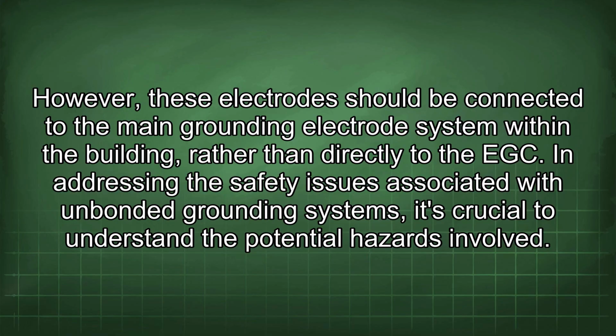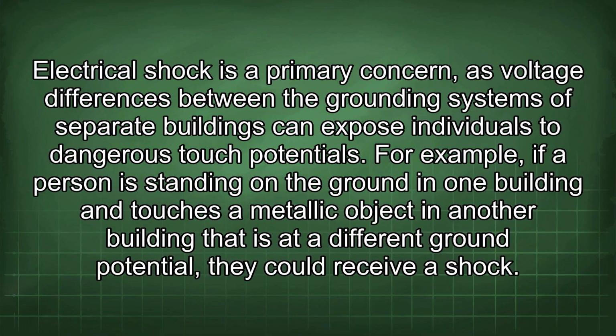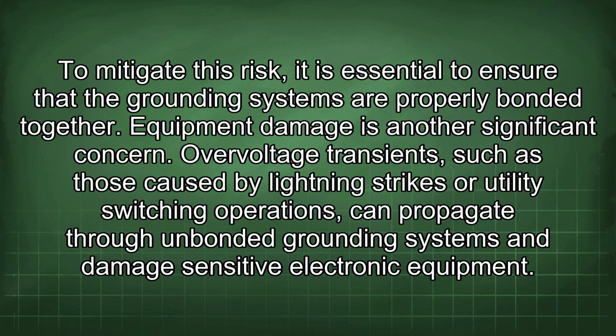In addressing the safety issues associated with unbonded grounding systems, it is crucial to understand the potential hazards involved. Electrical shock is a primary concern, as voltage differences between the grounding systems of separate buildings can expose individuals to dangerous touch potentials. For example, if a person is standing on the ground in one building and touches a metallic object in another building that is at a different ground potential, they could receive a shock. To mitigate this risk, it is essential to ensure that the grounding systems are properly bonded together.